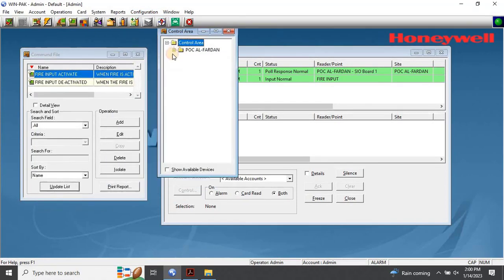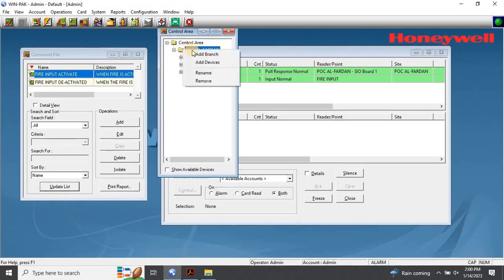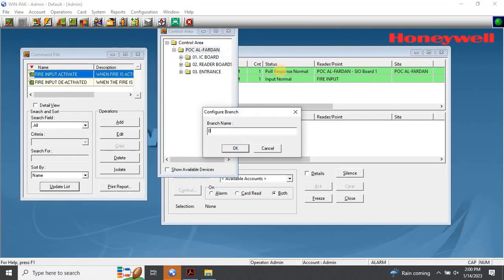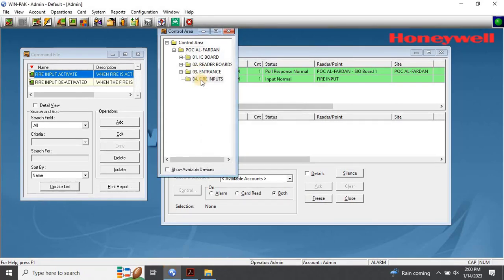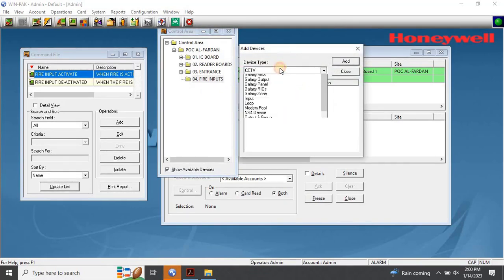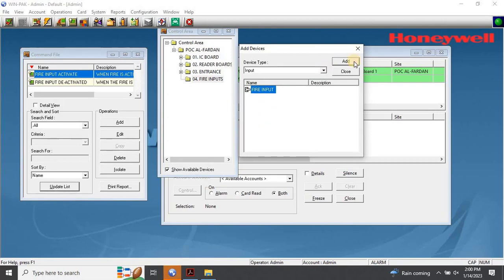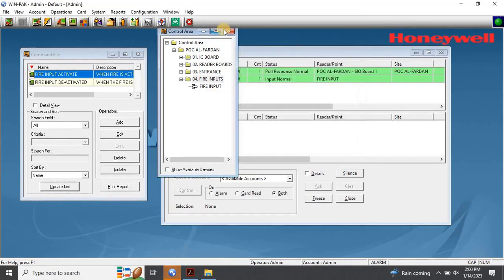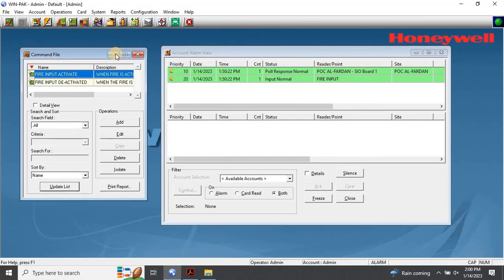The control area window will appear. Right-click on the site to which you want to add the branch and click Add Branch. The Configure Branch dialog box appears. Type the branch name as 'fire inputs' and then click OK. The branch will be listed under the site or branch in the control area window. To add a device to the branch, right-click on the branch and click Add Devices. The Add Devices dialog box will appear. Select the device type — the devices belonging to the selected device type are listed. Select the device to be added and click Add. To select multiple devices, press and hold down Control and click each device. Click Close to close the Add Devices dialog box. The devices will be displayed in the control area window.